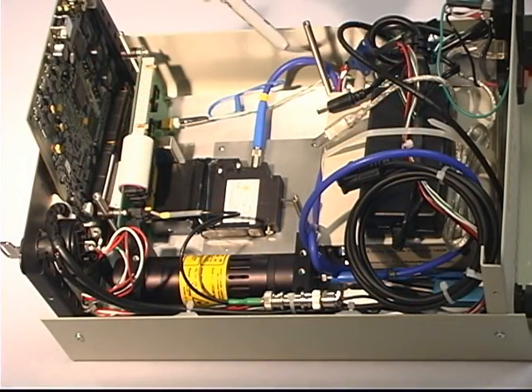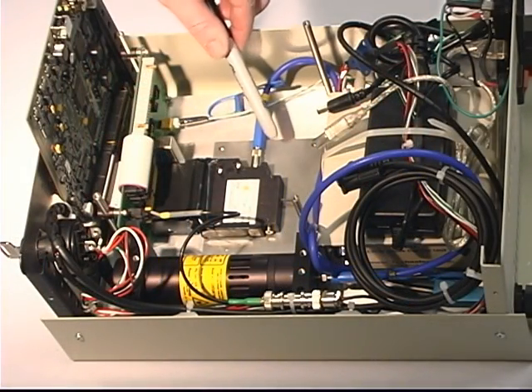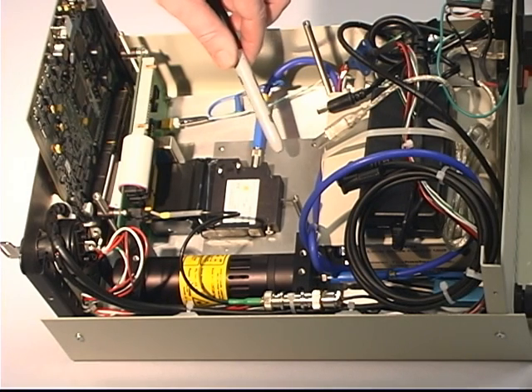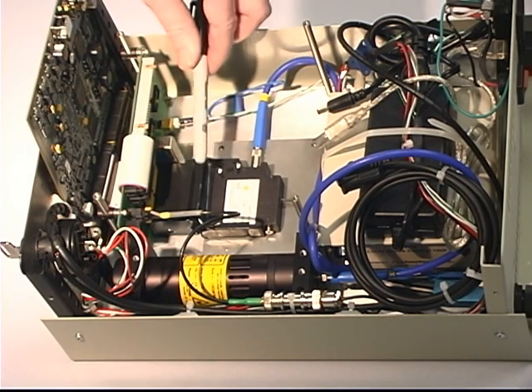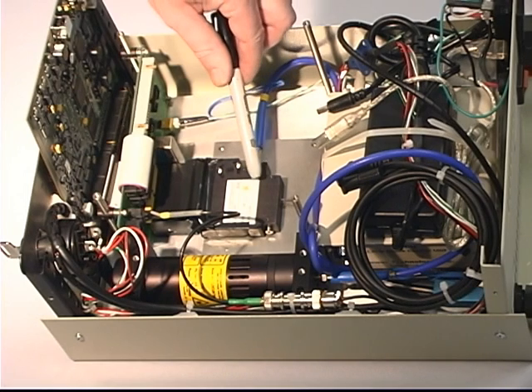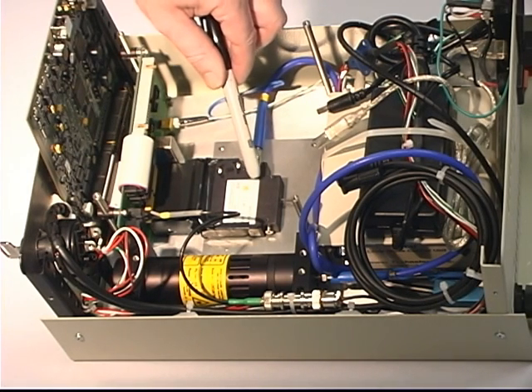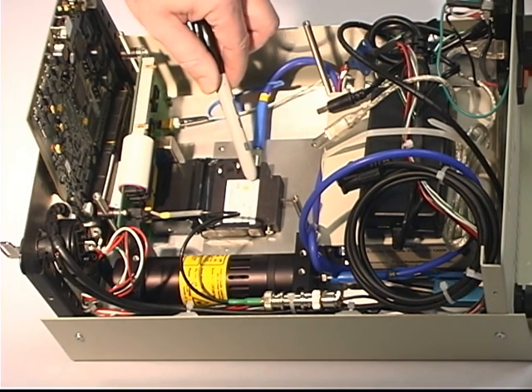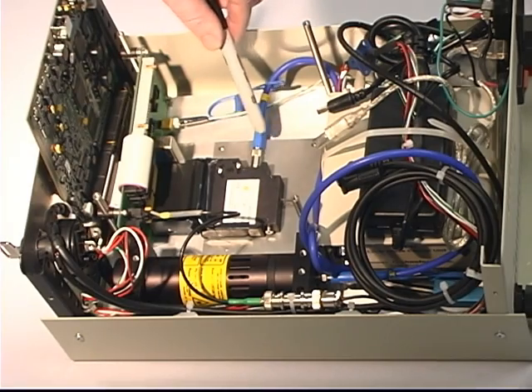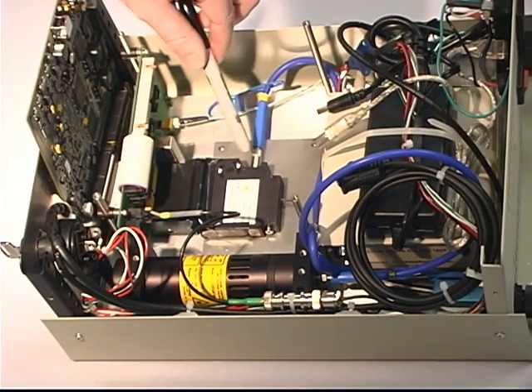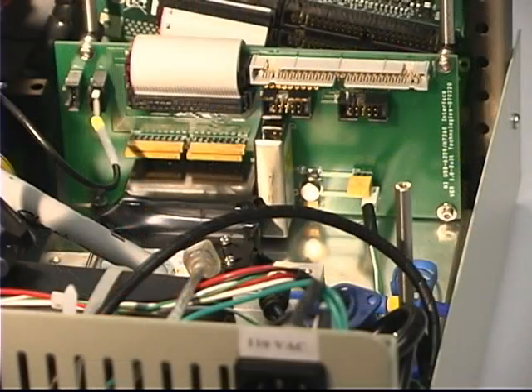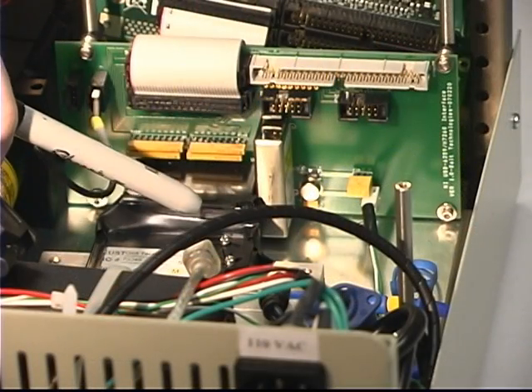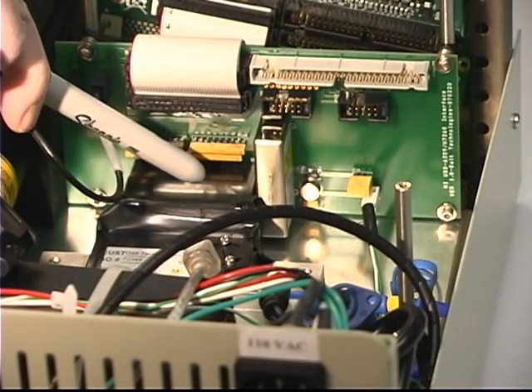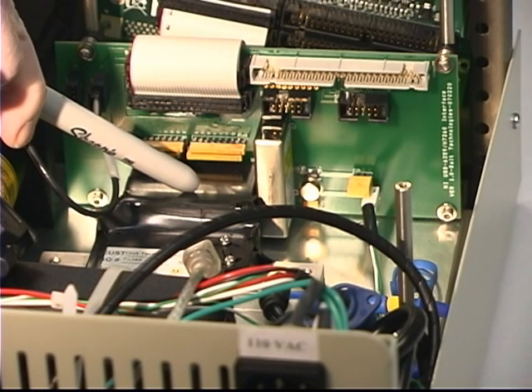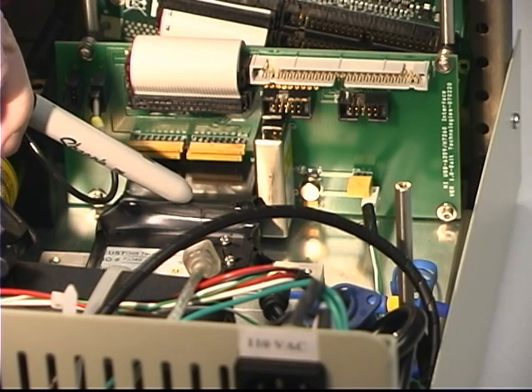Fluorescence collected by the reflection probe is input into the spectrometer by the 6 collection fibers, which are terminated in a custom SMA connector. This connector positions the 6 linearly arrayed fibers for input into the spectrometer. A 200 micron slit inside the spectrometer helps filter unwanted ambient light. A grating is used to separate the optical components of the LIF emission spectrum, and a mirror is used to focus the dispersed light across a 32-channel linear array detector.